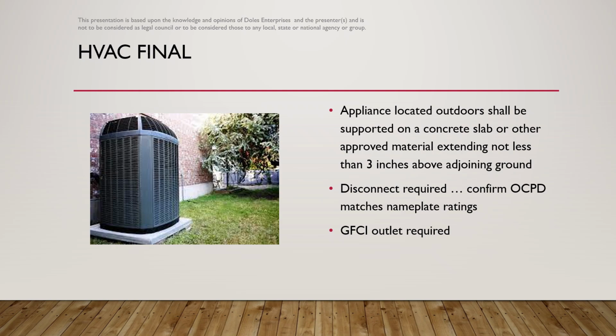For HVAC equipment located outside the building, the equipment shall be supported on a concrete slab or other approved material extending not less than 3 inches above the adjoining ground. A disconnect means must be required near the equipment. The overcurrent protection device must match the nameplate rating of the equipment served. A GFCI convenience outlet also must be required in the area of the equipment.